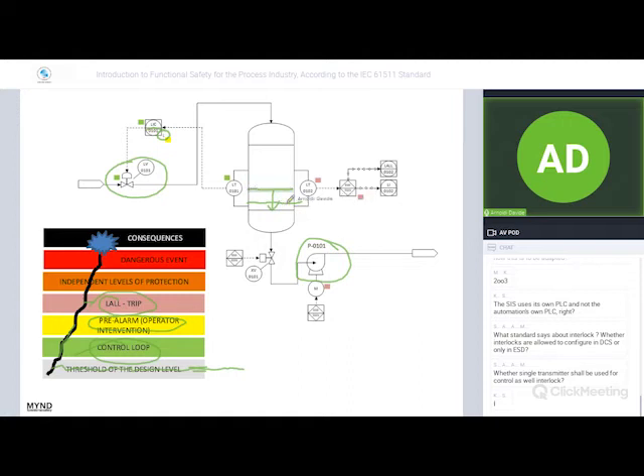In case of an existing safety instrumented function, we can close the valve and also stop the pump in order to protect it from cavitation. If not, because maybe we have a failure inside the safety instrumented function, we reach for sure the consequence. The consequence in this case is the pump replacement due to failure or damage inside the pump itself by cavitation.